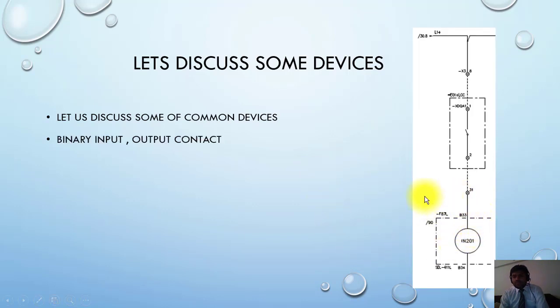The next symbol I am showing you, which is mostly used in drawings, is binary input, because now we have digital relays so we are using binary input. Here you can see this is LCC, local control cubicle. This is available with the GIS or outdoor switchgear. It's the local cubicle for the switch. One auxiliary contact, when it's closed, will energize this binary input. For example, if I configure this contact when the breaker is closed, this will close and I will get the signal in the relay to show that the breaker is closed. In this way, this drawing will work.